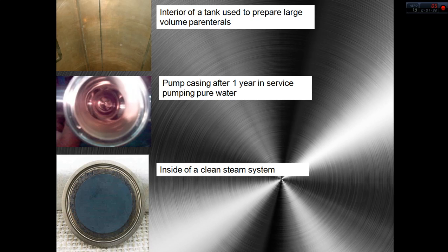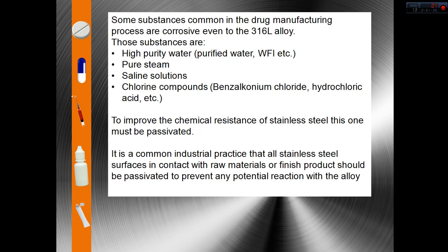There are many substances common in drug manufacturing that are corrosive to stainless steel. Some examples include high purity water — that could be purified water, water for injection, or any other kind of water — as well as pure steam, saline solutions, and chlorine compounds. That's why when we are using stainless steels, we want to get the best out of this alloy.